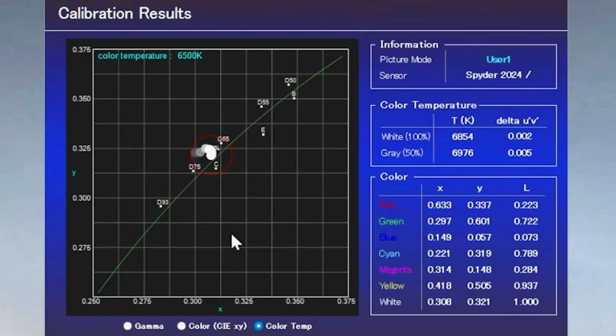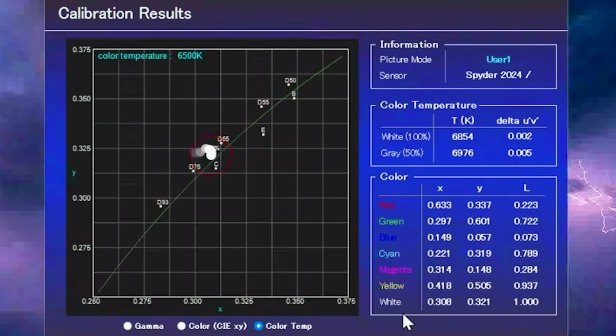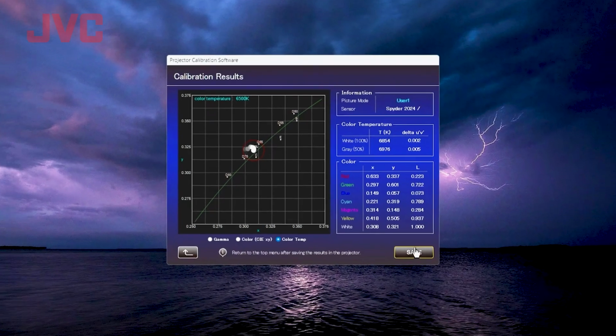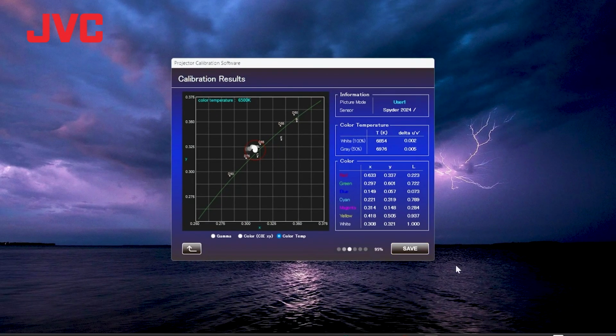Once you're done and everything looks good, you look at some images up on the screen and determine the grayscale looks good. Then you can go ahead and save, and it's going to reload all the calibrated data back into the machine, so it'll be permanently installed in the machine. Once you've done this, you can actually get back to where we started by going to the import function in the settings menu of the calibration software. So we're going to hit save here. It just takes a minute.